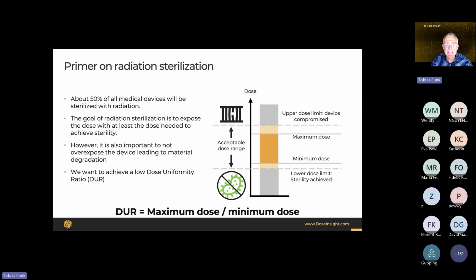50% of all medical devices that need sterilization go through radiation sterilization. And the goal of radiation sterilization is to basically get at least the minimum dose to make the product sterile. And at the same time, we don't want to overdo it. We don't want to overdose the product, because that can damage the integrity. So we define a minimum and maximum dose where we need to stay in. And we also can express that as the dose uniformity ratio, where we essentially divide the maximum dose by the minimum dose. And we want to stay below this defined level by this consideration.